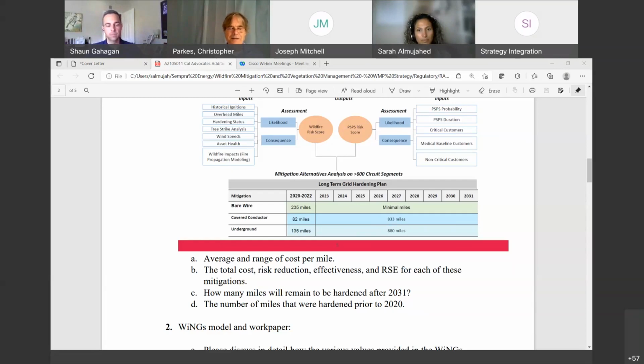Can you give us a sense of what that categorization or distribution of faults are? Is wires down half of those faults, 10%? I would have to look at the total summary. We bucketed a lot of them - there were weather-related faults, third-party contact faults, foreign object and line faults, and equipment failure faults were some of the buckets. Wires down would be a small percentage of the overall faults that we have.